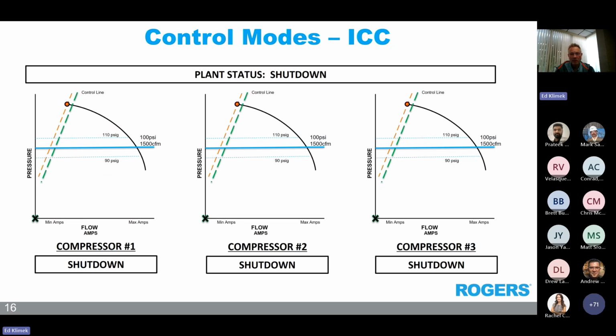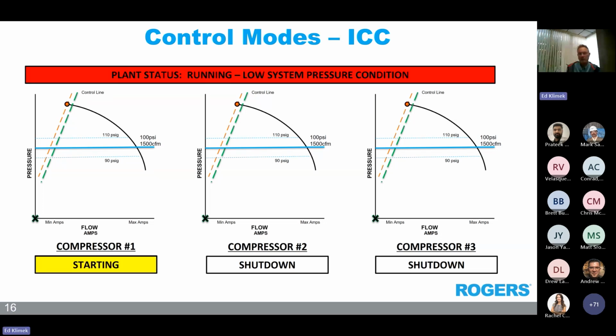So this animation will show the operating of each compressor in a lead trim style. And then the next part of the animation will show more of a load sharing. So I'll start the animation. With the plant system running on a low system pressure, it starts up compressor 1. The system pressure is still low. The compressor will load to its maximum operating point within PBO that we discussed earlier. So it's running at 110 psig right now.